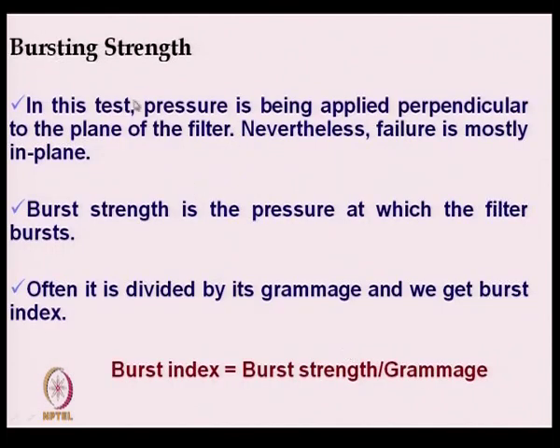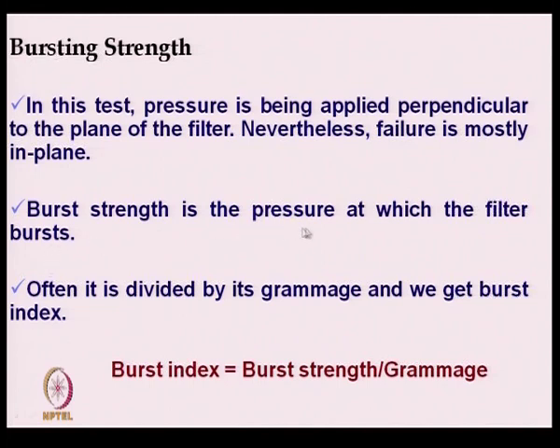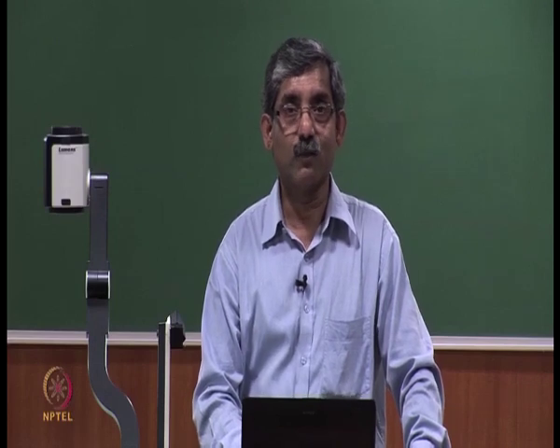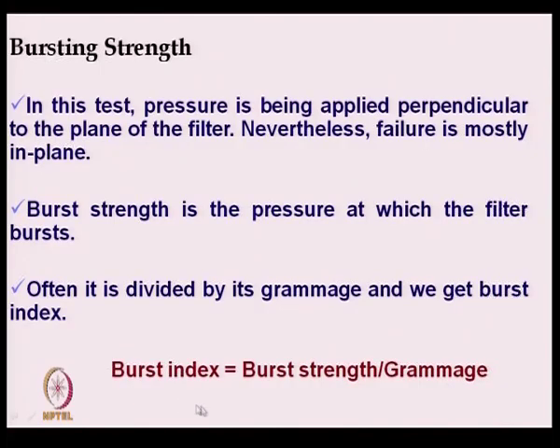The next parameter which is very important for filter fabric is bursting strength. In this test, pressure is applied perpendicular to the plane of the filter, but the failure is in the in-plane direction. Burst strength is the pressure at which the filter bursts; it is often divided by the grammage to get the burst index, which is the normalized value irrespective of grammage.